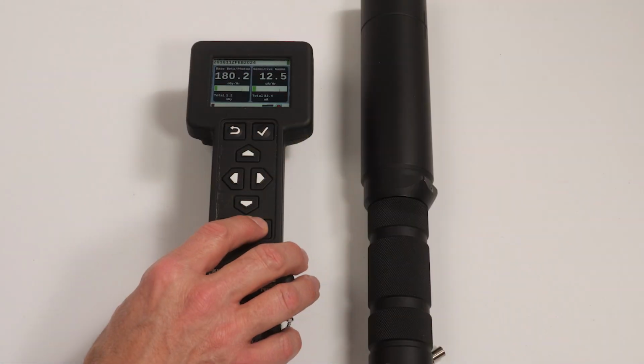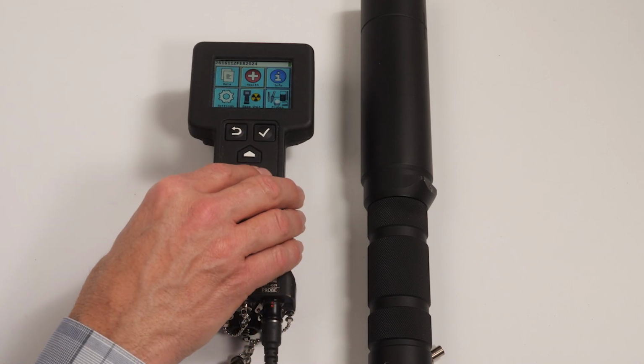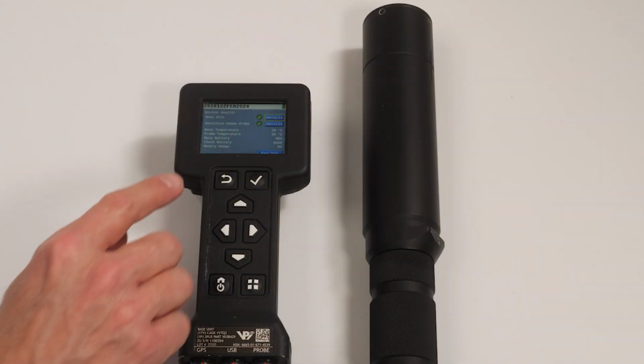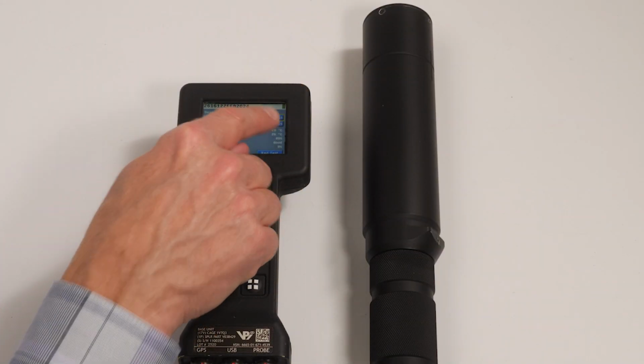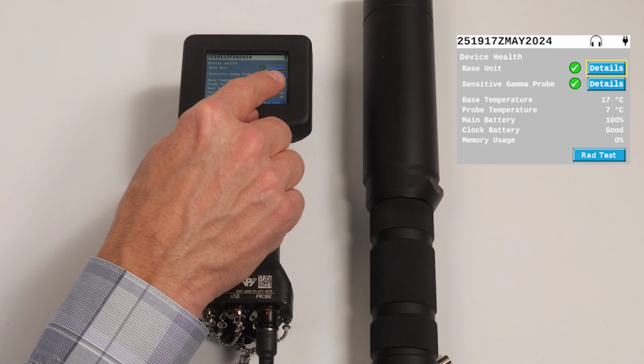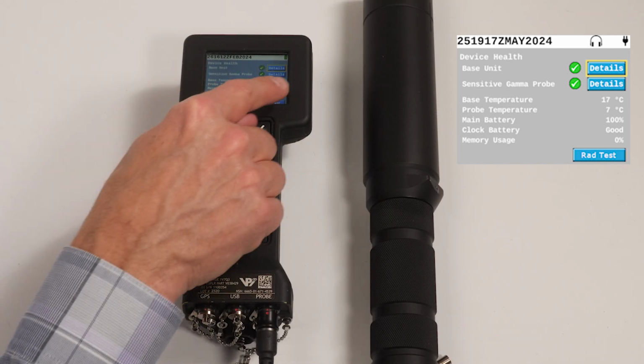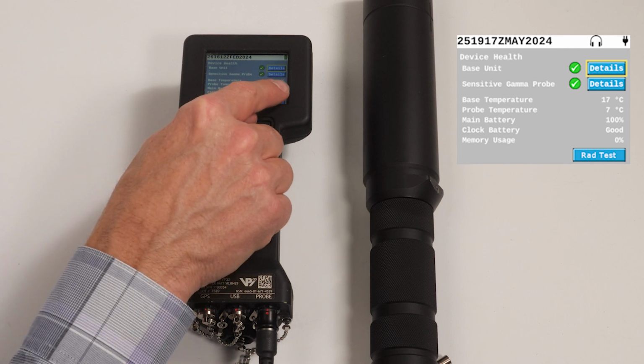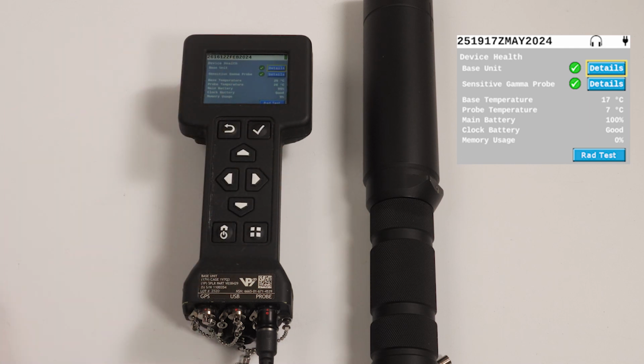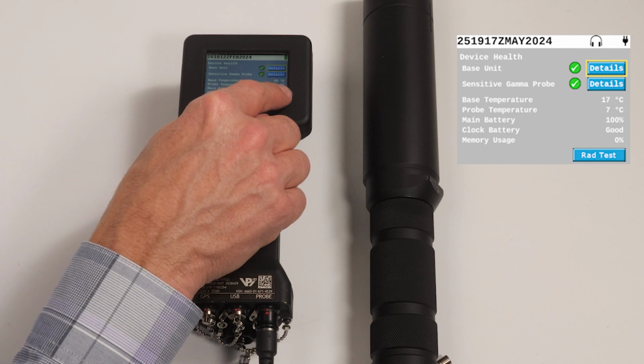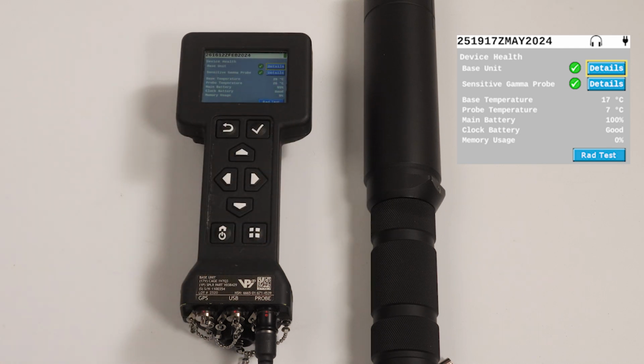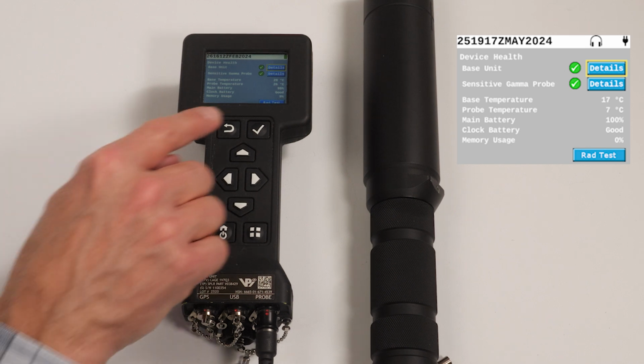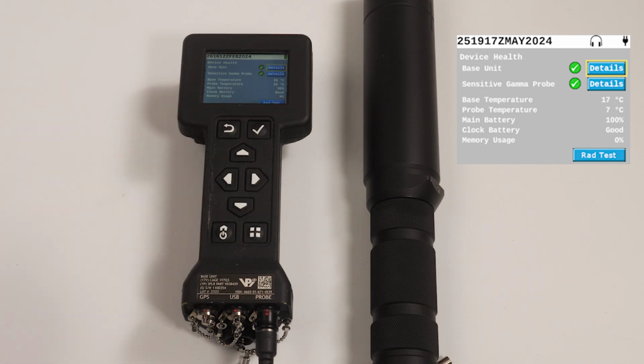View system health details on the health screen. Press the menu key to access the main menu, or highlight health and press the enter key. On the health screen, you can check the following items: base unit details and attached probes details, the base unit's temperature and attached probes temperature, main battery levels or the battery life of the 4 AA batteries powering the base unit and any attached probe, the clock battery status, which will either be good or low, memory usage of stored data logs, and you can perform a RAD test.